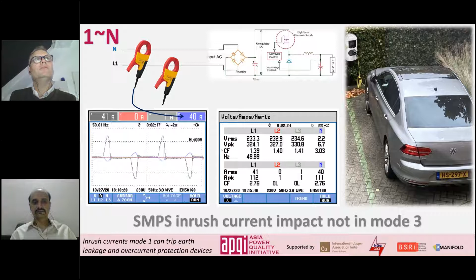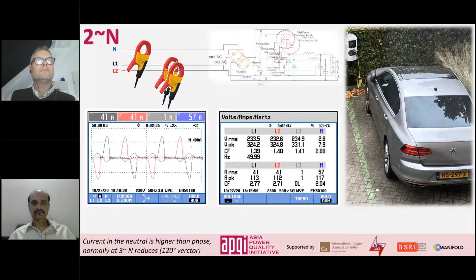But normally, when we have 3-phase systems and they are in balance, with the current and the voltage phasors 120 degrees forward and backward to each other, and you have the same current in all lines, then the current in the neutral is almost zero. So let's look at it. Let's put on the second phase. And what you see now is that there is more current in the neutral than in the three phases together.